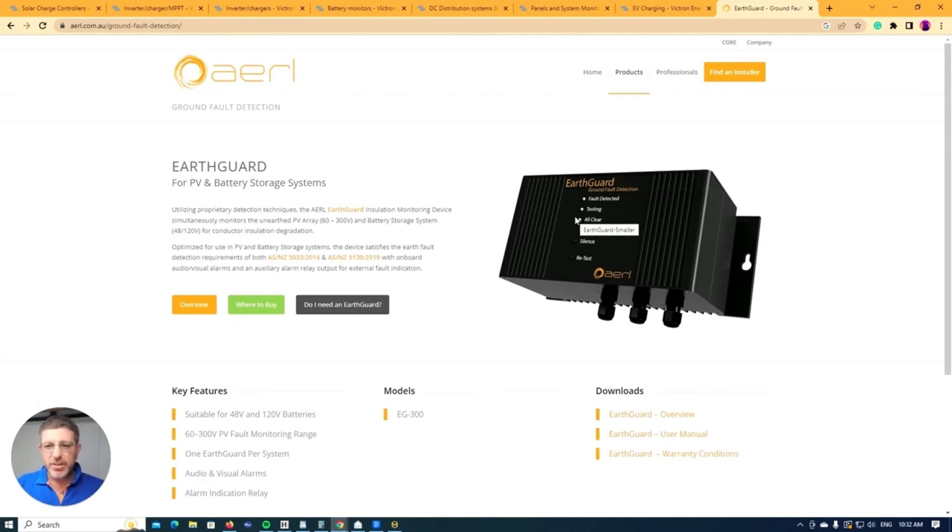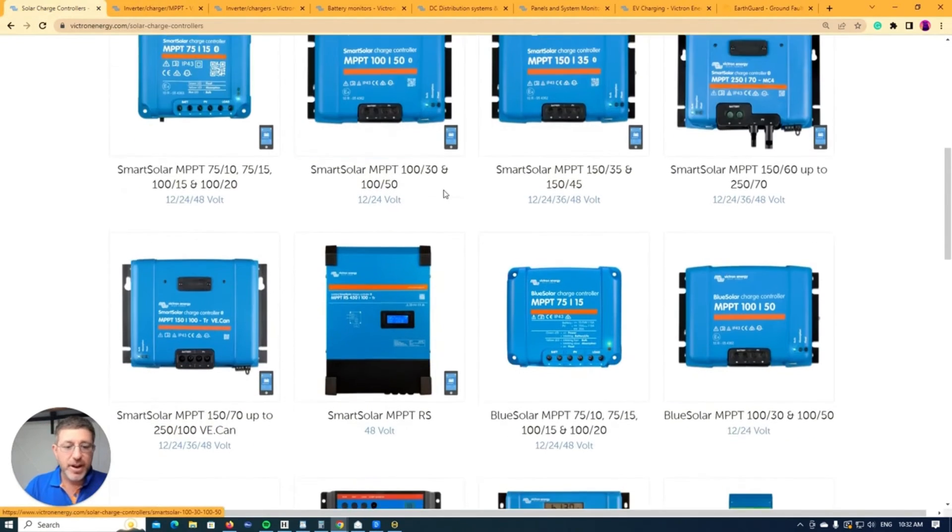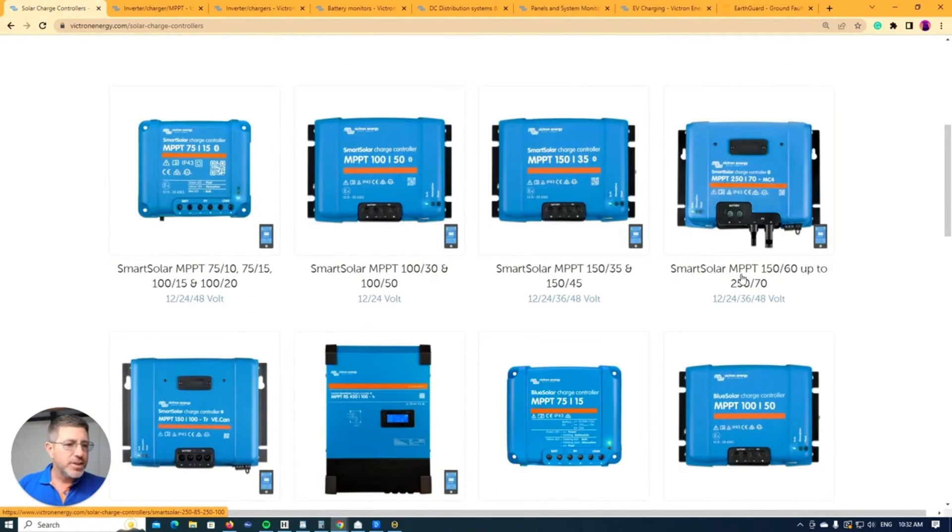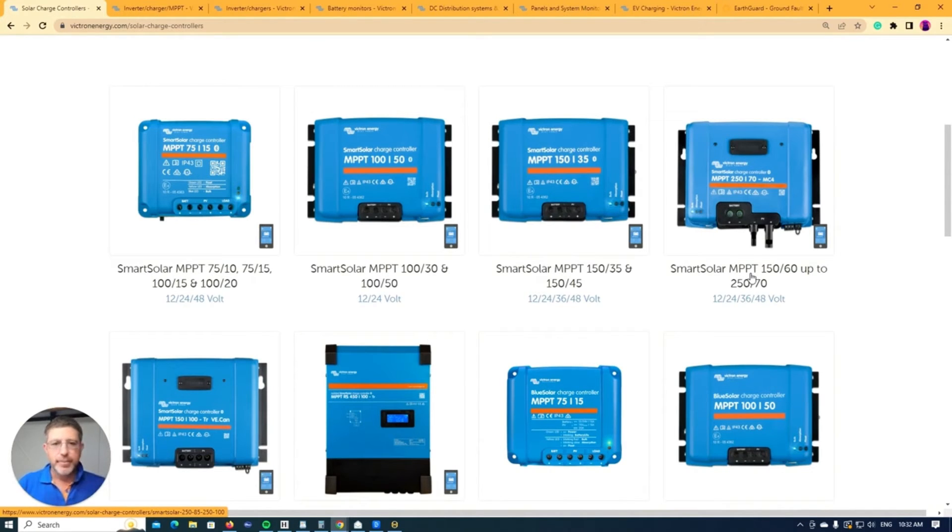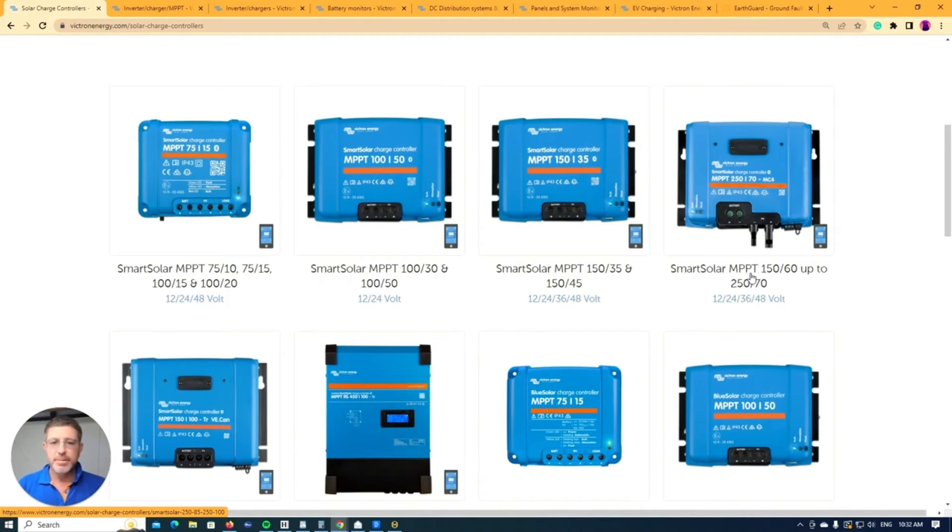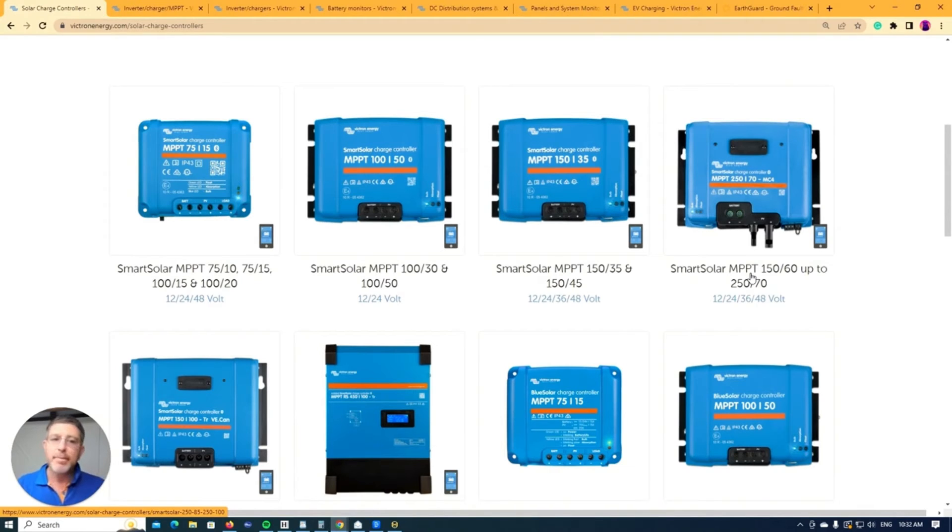They're worth about $600, I think here in Australia. And as an example in Australia here, if you want to use these 250/60 or 70 MPPTs, you'd require to put an earth fault alarm in there to be able to use it and comply with the Australian rules and regulations. But if you're in the States or the UK, I think the UK might have a similar rule, but the States don't. You can just whack them up and you're fine. You don't need to worry about the earth fault alarm.